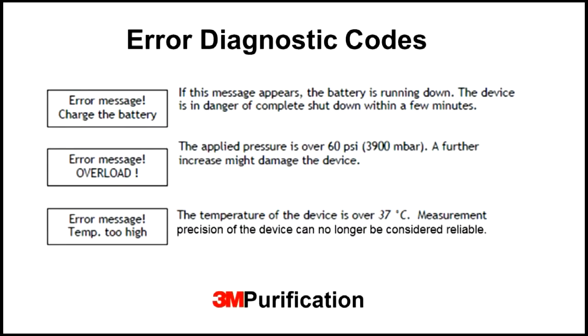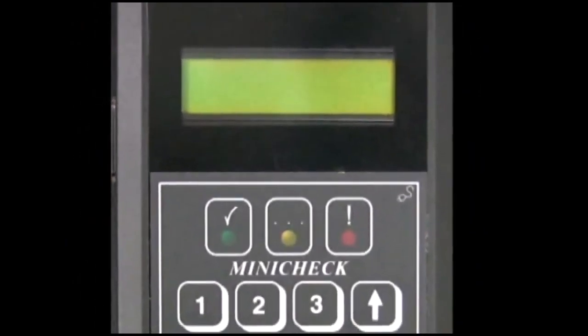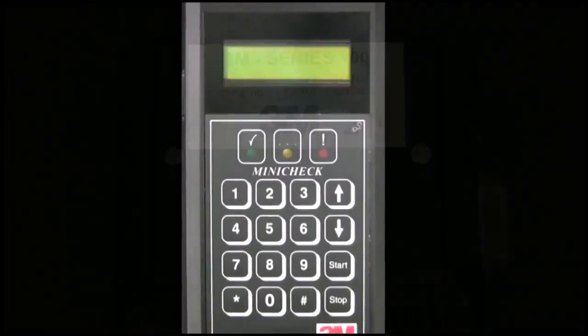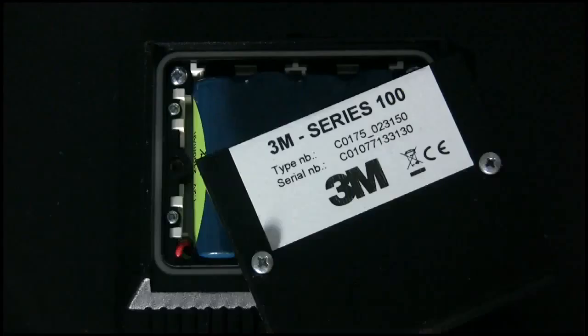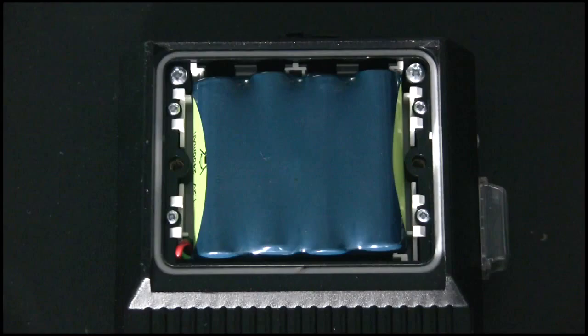Following are typical error diagnostic codes that may display on the device and an explanation of each. The first message is an indication that the battery life is low. In the event this message appears, the device should immediately be connected to AC power and/or charged. In the event the device does not activate when connected to AC power or fully charged, the battery supplied with the device may be exhausted. The battery typically lasts two years. The battery can be accessed and replaced by removing the battery panel on the back of the device. Because of the complexity of the wiring involved, it's recommended to contact 3M Purification Technical Support to complete the task of battery pack replacement.